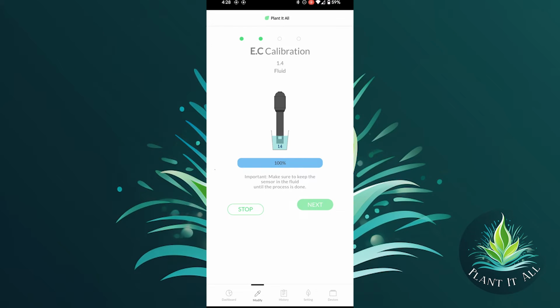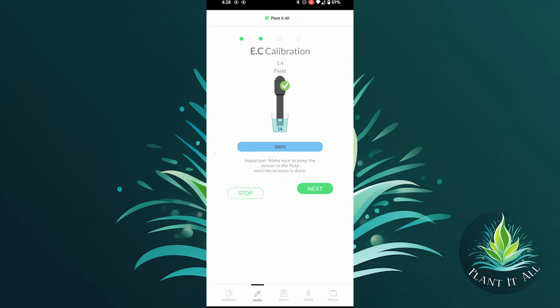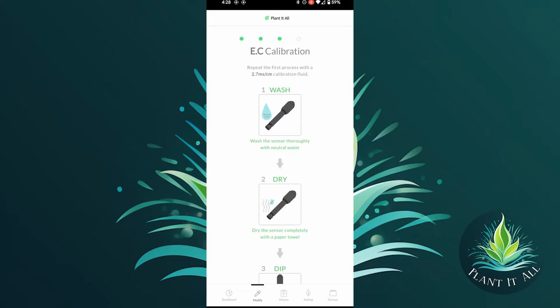All right, there we go, 100%. We're good to go. We got the green check mark. Let's go ahead and hit next and move on to the next step. Same thing here. So we're just moving up to the 2.7 solution. Wash the probe in your distilled or your RO water. Give it a little bit of a gentle dry off. And then you're going to dip it into your solution.